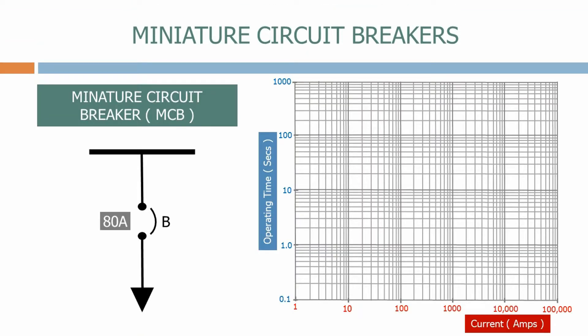Here we have a type B MCB rated at 80 amps protecting a feeder circuit. Let's look at the typical characteristic. As we can see the top half of the characteristic is very similar to the curve we've seen on the fuses that we looked at previously.